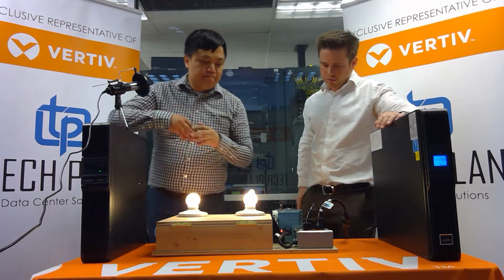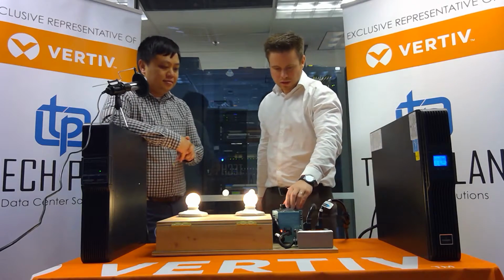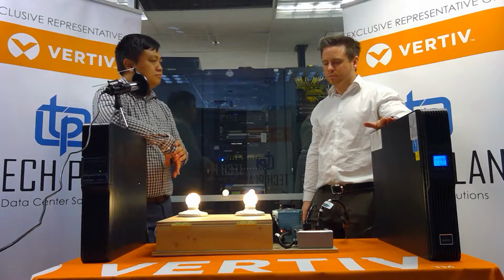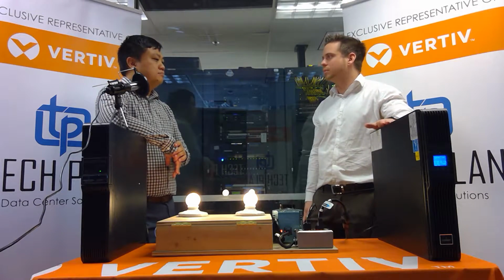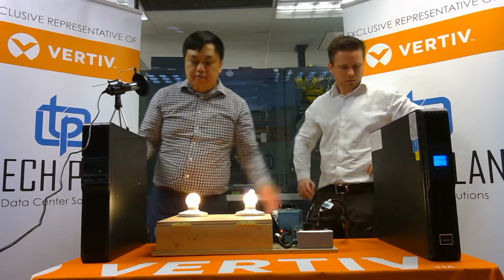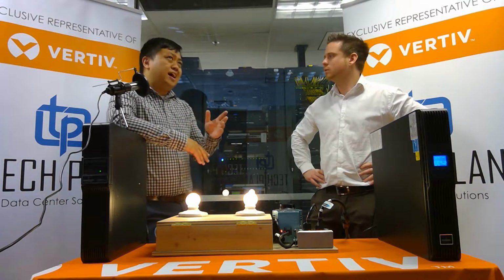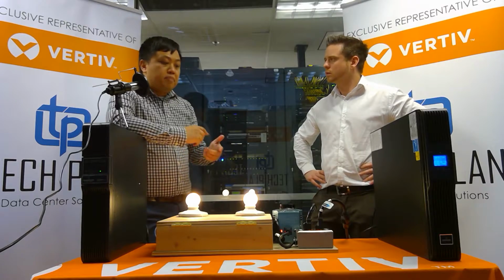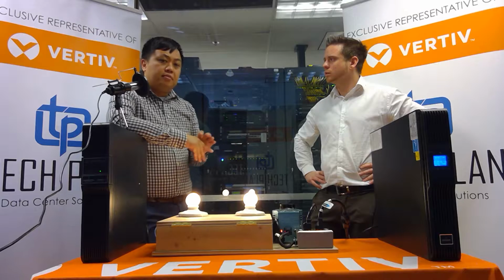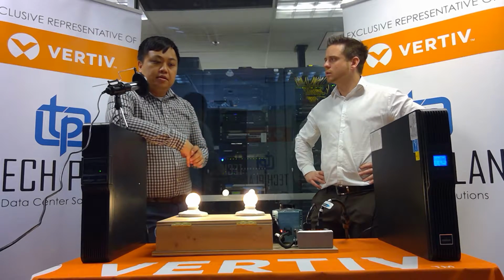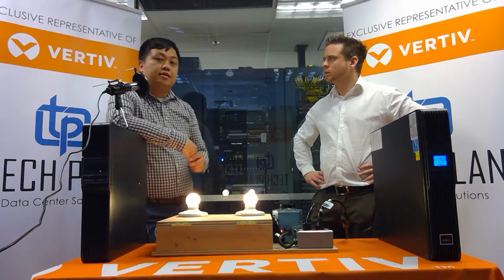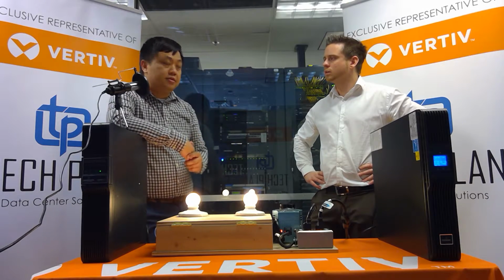Perfect. Interesting stuff. And so, when I get one of these UPSs, what can I do in terms of monitoring, for example? What are my options? So both of these UPSs have an IntelliSlot card on the rear, and we provide IS Unity DP cards. So BACnet IP, Modbus, SNMP, literally any type of third-party monitoring system can communicate with these. And of course, here at Vertiv, we do have the Trellis and SiteScan and Nform systems that are fully compatible with these as well.